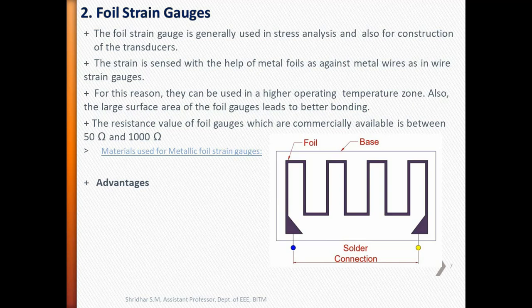The characteristics of foil gauges are similar to those of wire wound strain gauges and their gauge factor is typically the same. The resistance value of foil gauges which are commercially available is between 50 ohms and 1000 ohms. The maximum gauge current is about 30 milliamps. Maximum strain for plus or minus 1% linearity is about plus or minus 0.3%, and strain variation up to at least 50 kilohertz can be measured.